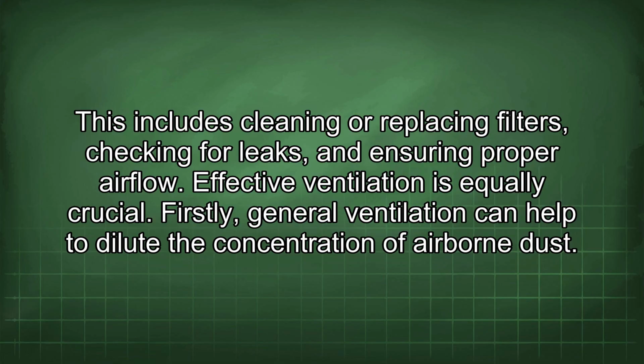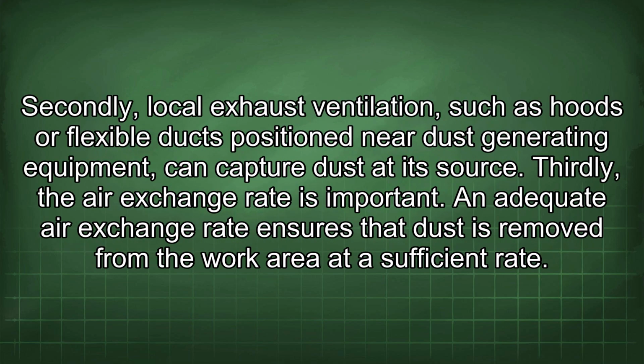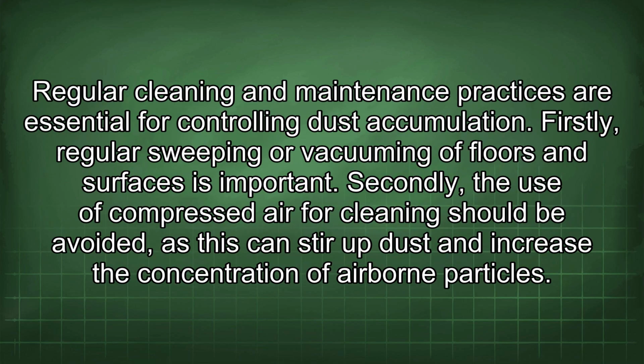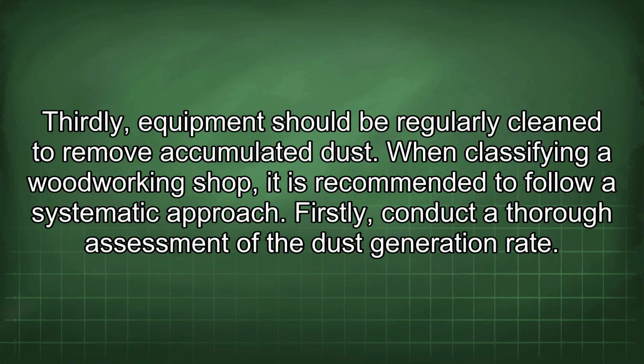Effective ventilation is equally crucial. Firstly, general ventilation can help to dilute the concentration of airborne dust. Secondly, local exhaust ventilation, such as hoods or flexible ducts positioned near dust-generating equipment, can capture dust at its source. Thirdly, the air exchange rate is important. An adequate air exchange rate ensures that dust is removed from the work area at a sufficient rate. Regular cleaning and maintenance practices are essential for controlling dust accumulation. Firstly, regular sweeping or vacuuming of floors and surfaces is important. Secondly, the use of compressed air for cleaning should be avoided, as this can stir up dust and increase the concentration of airborne particles. Thirdly, equipment should be regularly cleaned to remove accumulated dust.